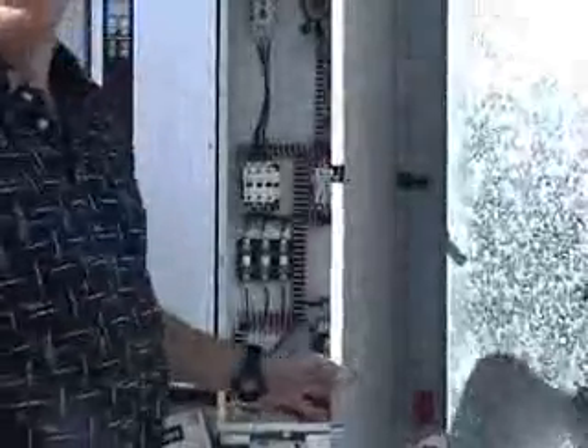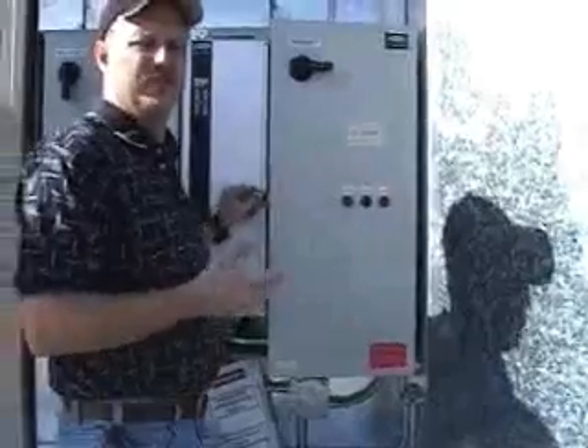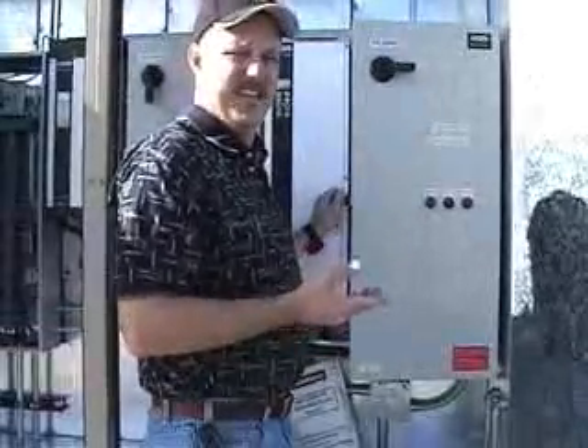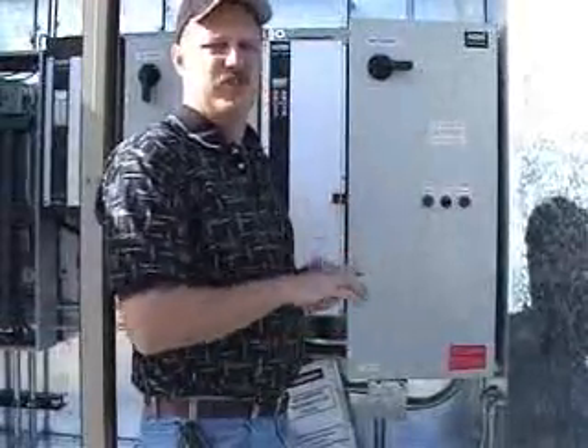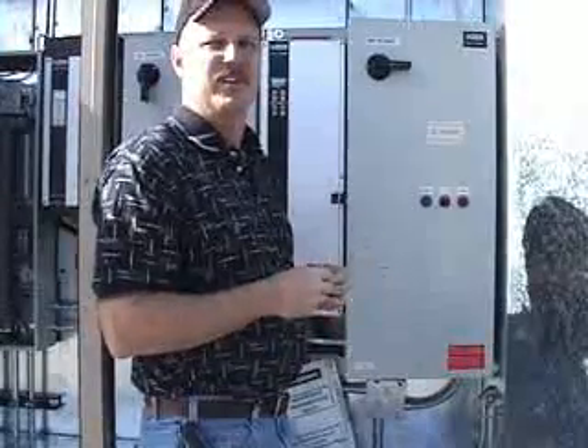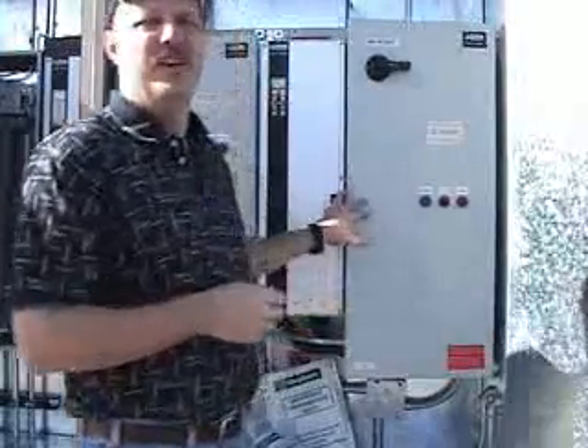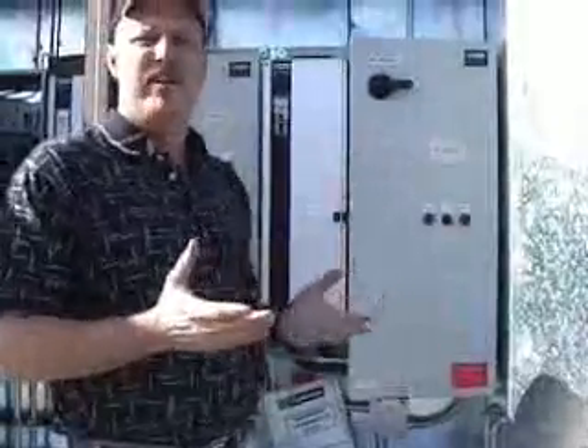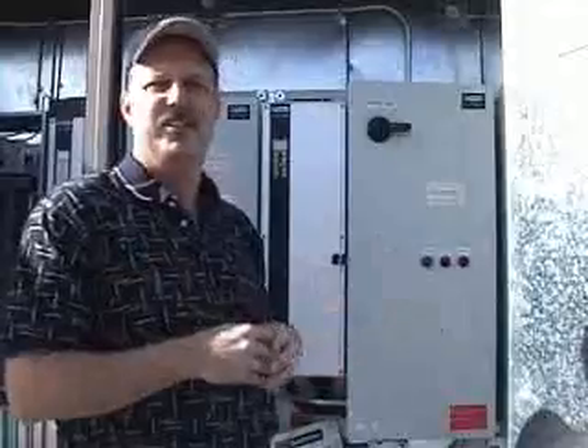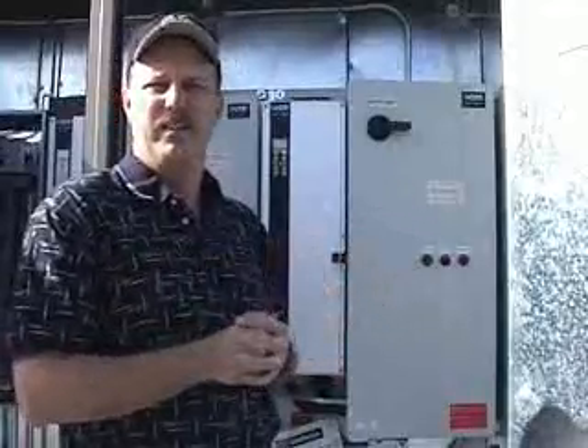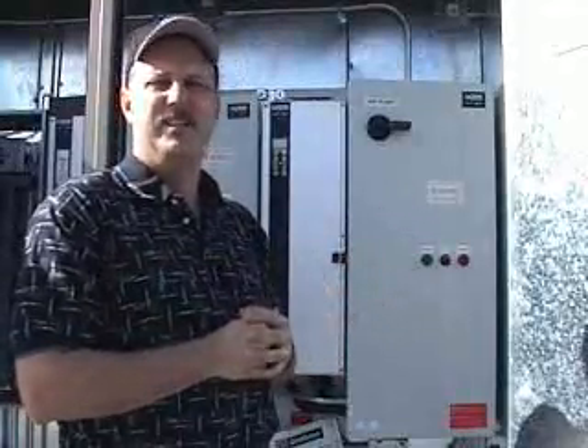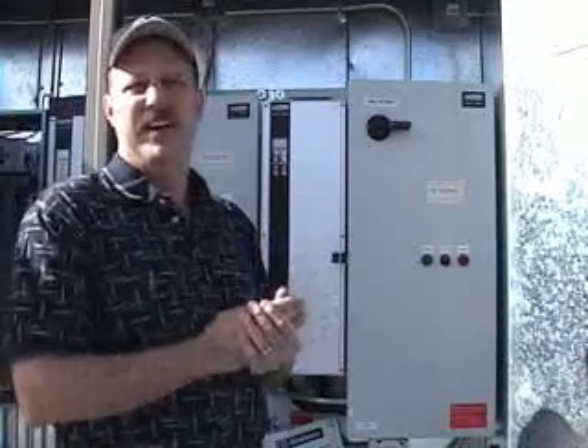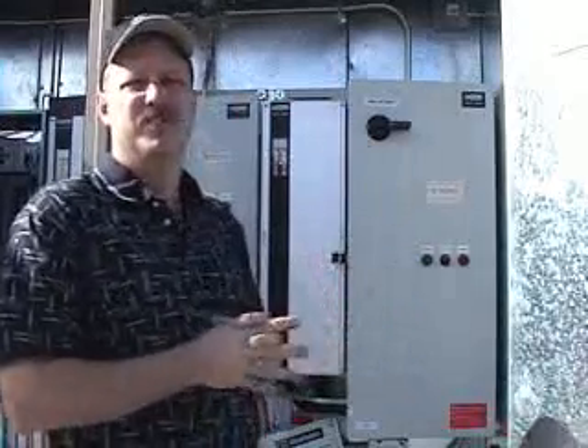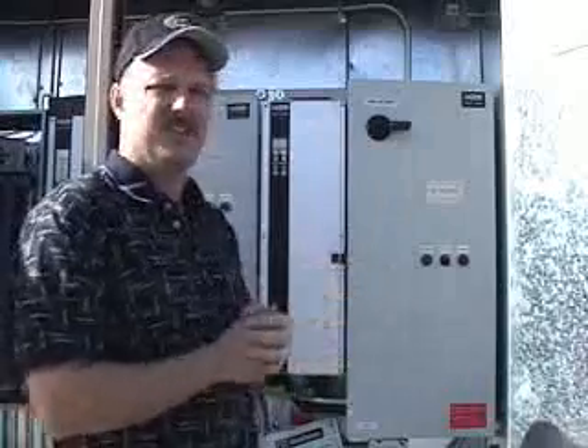But what we wanted to look at today was how a frequency drive works and how it changes the amplitude and frequency of the voltage signal in. By doing that, we can control very accurately the speed of our motors. So that's what these devices do. We control the speed because we don't always want our fans running at 100%. There are times when there's nobody in the building, but we need a little ventilation, so we'll back those fans off to 20, 30, 40%. That's the reason for these. It's a money-saving device too. It costs a lot of money to run these big motors all the time, so that's what this does.